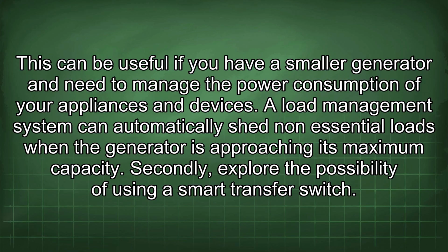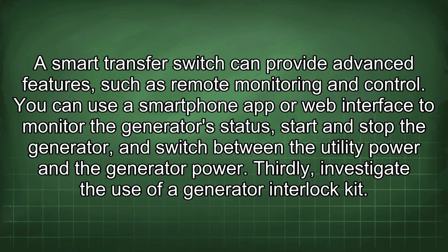A load management system can automatically shed non-essential loads when the generator is approaching its maximum capacity. Secondly, explore the possibility of using a smart transfer switch, which can provide advanced features such as remote monitoring and control. You can use a smartphone app or web interface to monitor the generator's status, start and stop it, and switch between utility power and generator power.